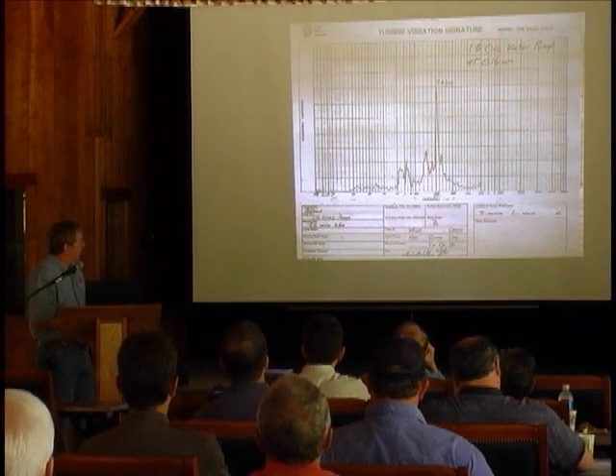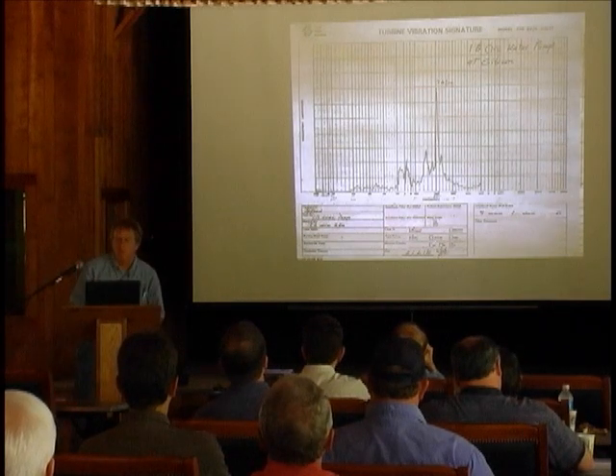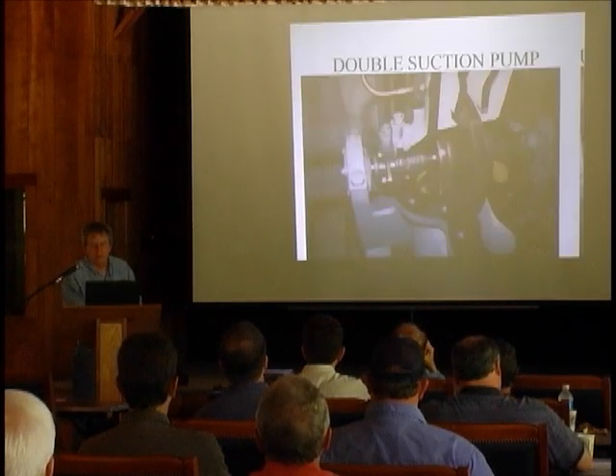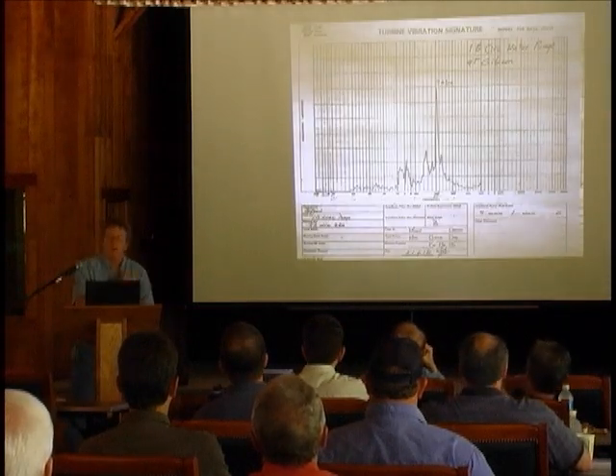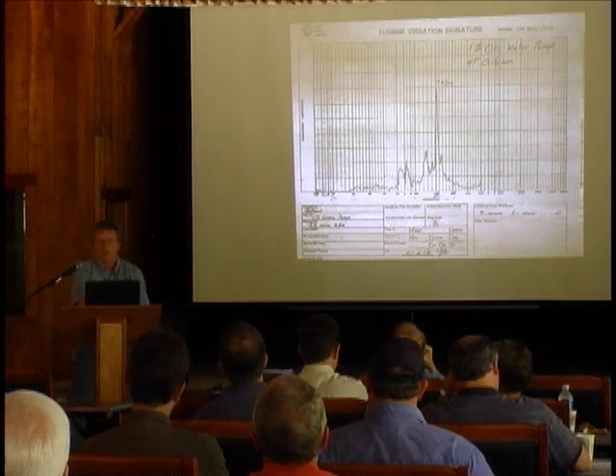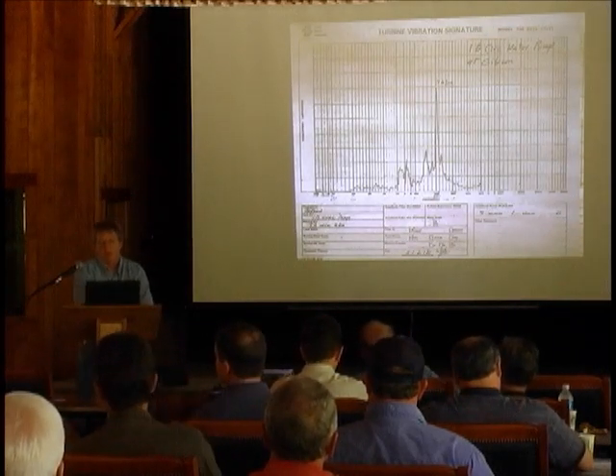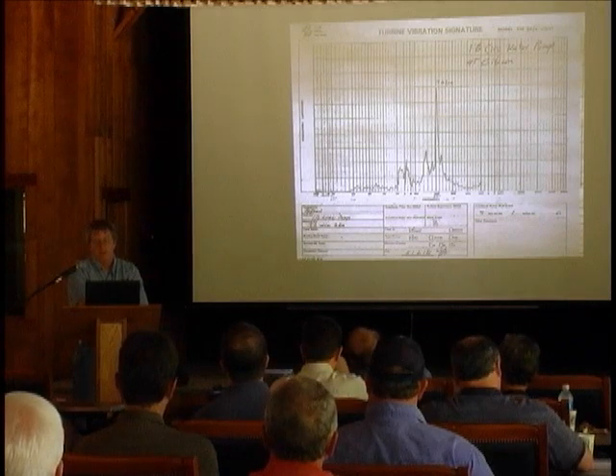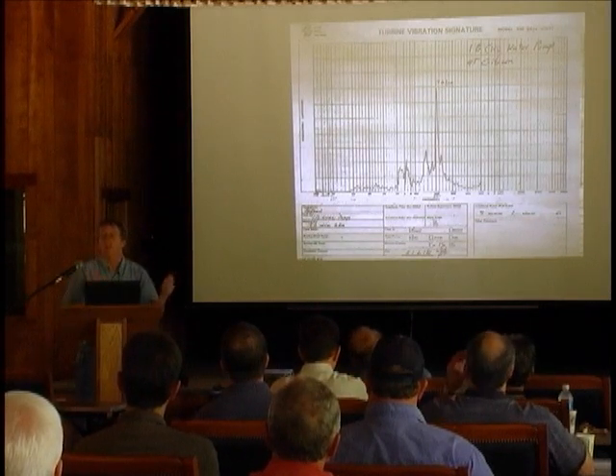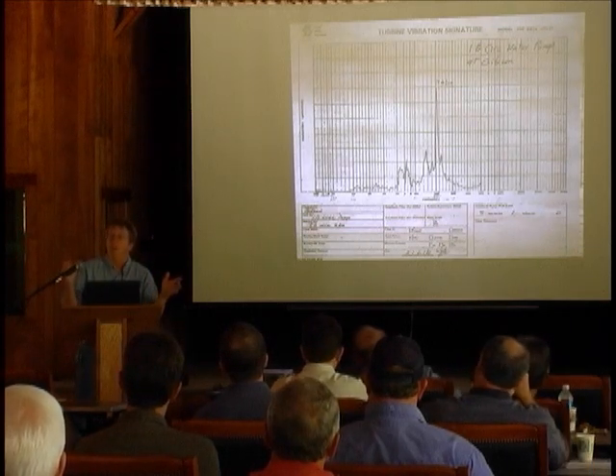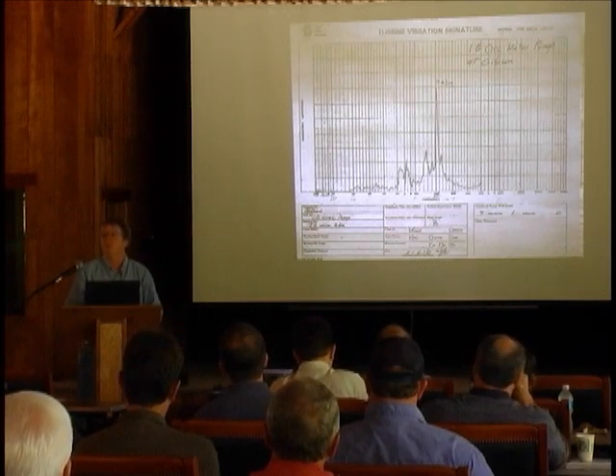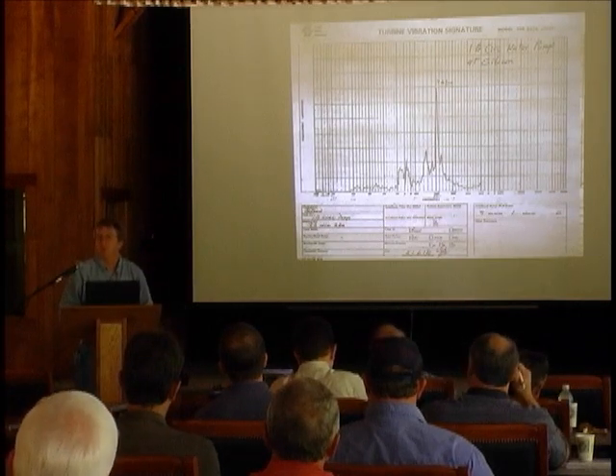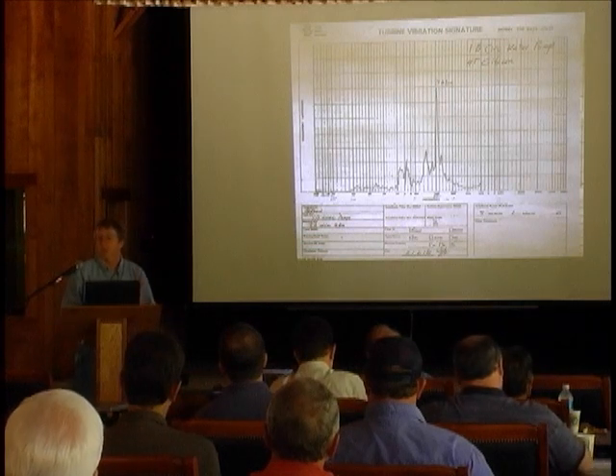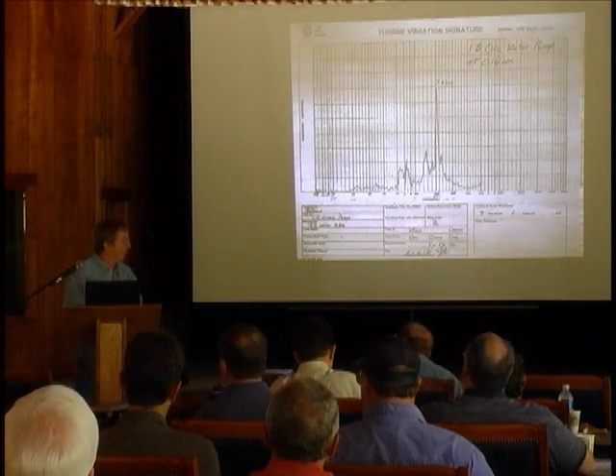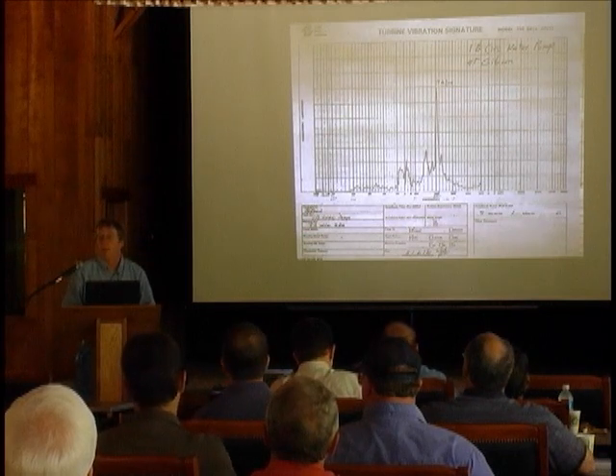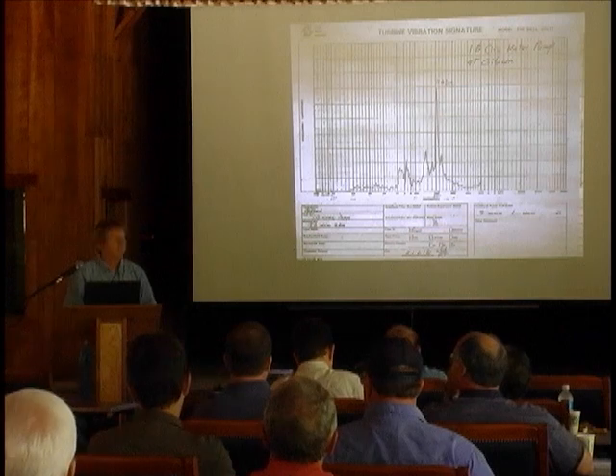I looked at it, I said, well, what could cause broadband? I said, well, if the pump was in a run-out condition, that might do it. I don't have the drawing here. But whenever I work on pumps, unless it's just some bearing going out, the first thing I always want is a pump head curve. You need to know the flow head curve. In other words, I've got this pressure on the pump, what's supposed to be the flow, what's my best efficiency point. That's where the angle of the fluid coming off the impeller matches the angle of the volutes. There's only one place for a constant speed pump. And if they're not operating at that point, then you know you're going to have vibration and trouble.